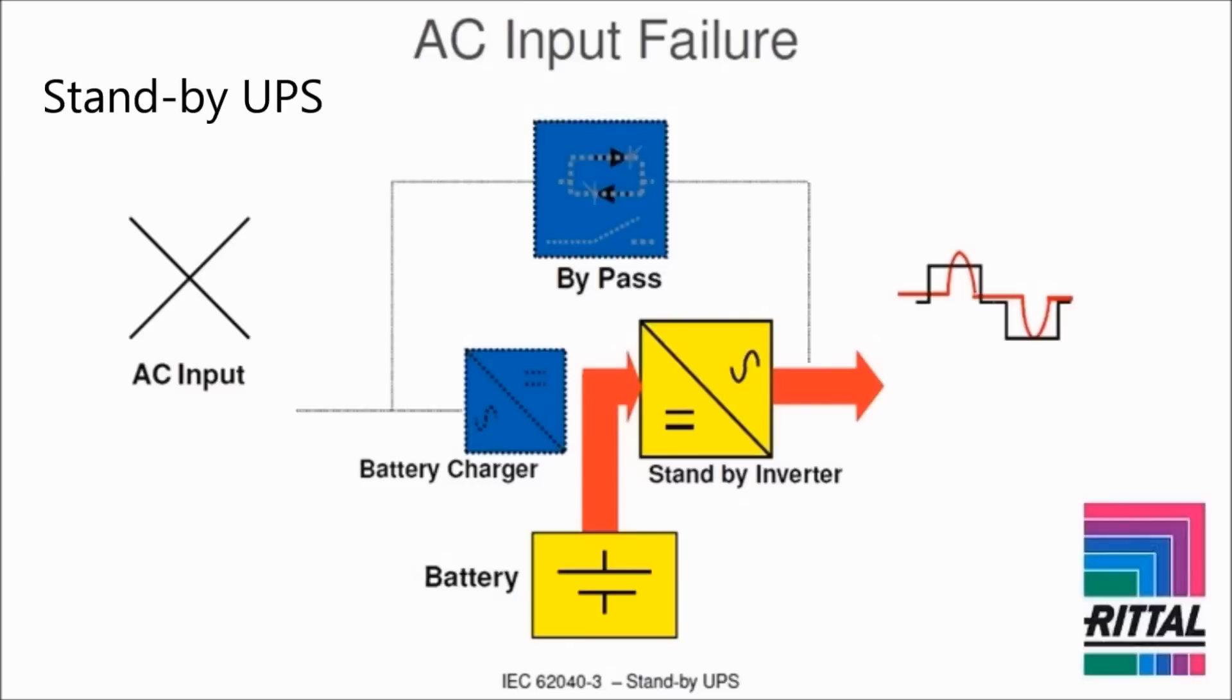UPS devices of this type are often cheap, but the stepped square wave output introduces high-frequency noise to the connected equipment, which is likely to cause malfunction and even permanent damage to sensitive IT equipment. There is also a change over time between the failure of mains power and inverter startup, which can cause IT equipment to reboot.